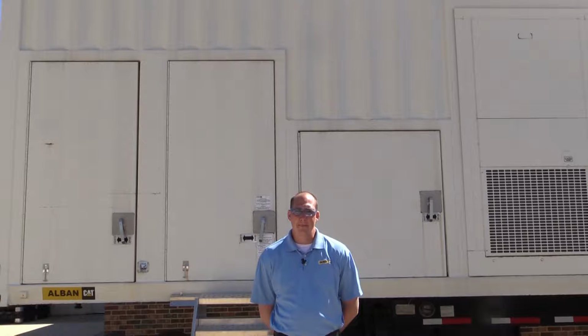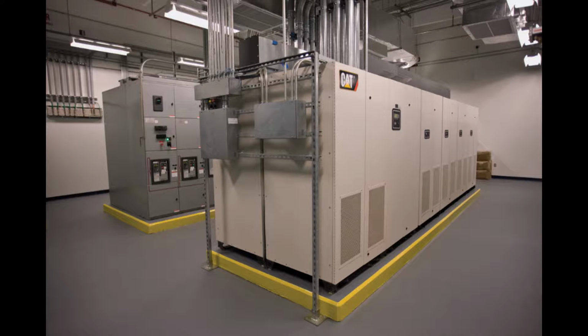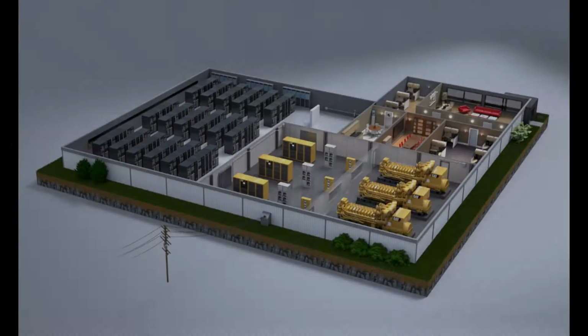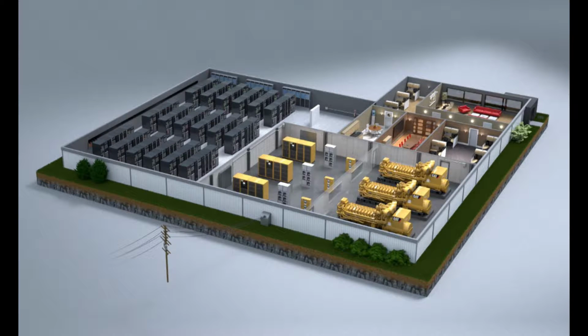I'm here to talk to you today about the Alban CAT Rental UPS system. You might ask yourself, what is a UPS? A UPS, or Uninterruptible Power Supply, is a piece of electrical equipment that provides emergency power to a load when the input source, typically utility power, fails. A UPS differs from an emergency power system or standby generator in that it will provide instantaneous, seamless protection from input power interruptions by supplying stored energy.